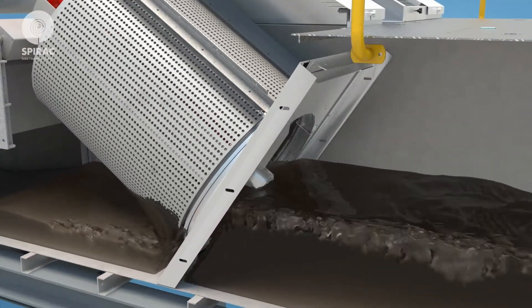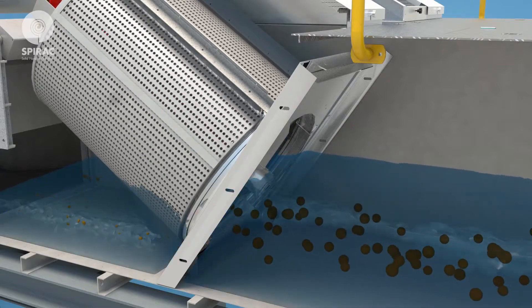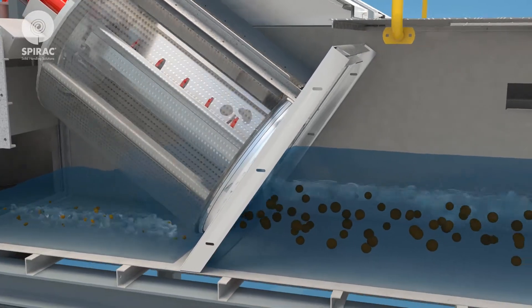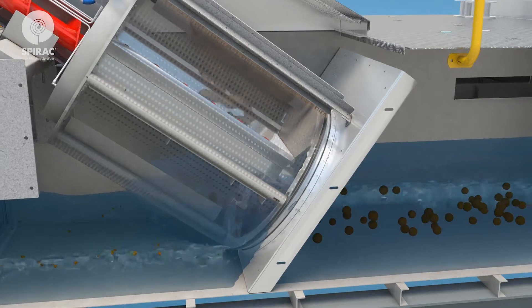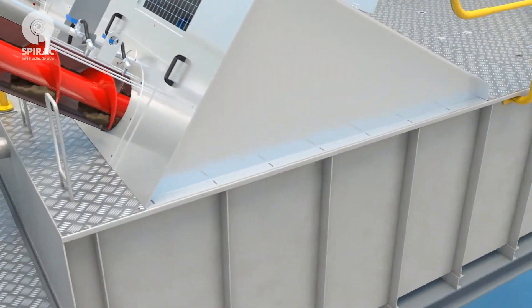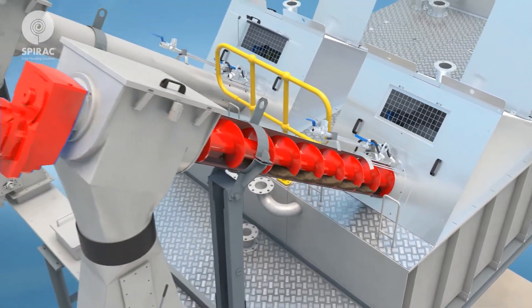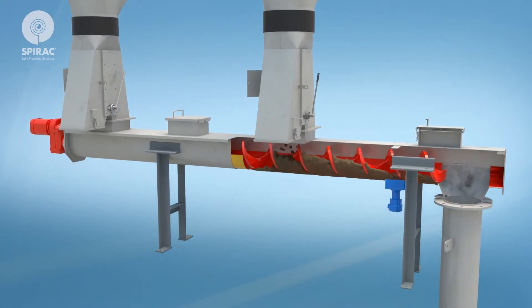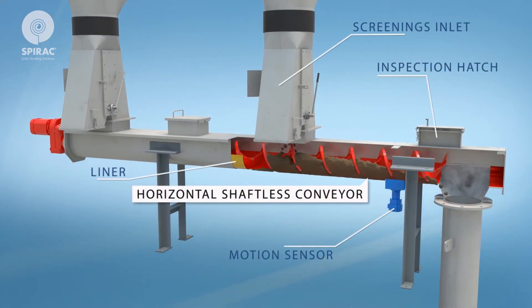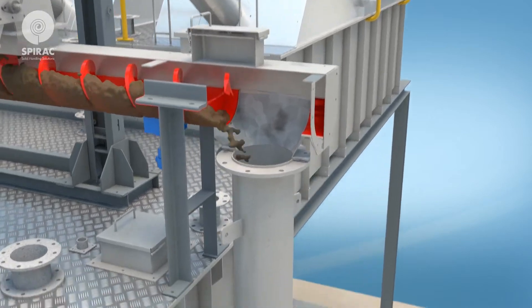The two drum screens work in a duty-standby configuration to remove solids larger than 2.0 millimeters from the incoming flow. As soon as the sewage level reaches a predetermined level, both fine screens will be running. Screenings are separated from the liquids and transported when discharged to a horizontal shaftless screenings conveyor.